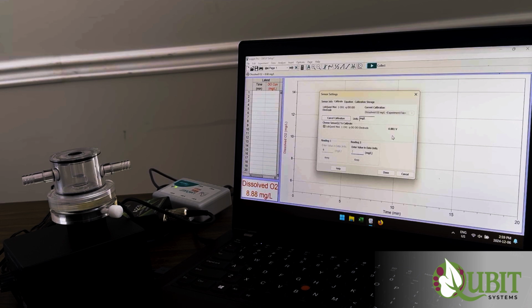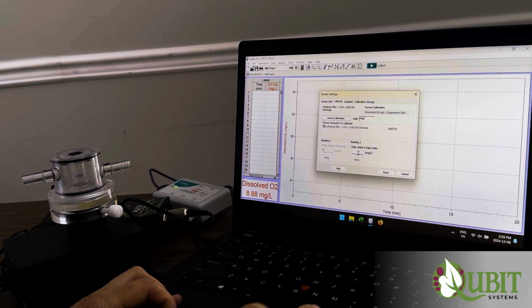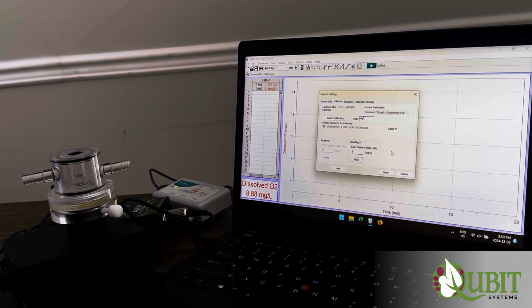So you wait until this voltage stabilizes, and under reading 2 you will enter 0 milligrams per liter, but don't click keep until the reading is stable. So you keep monitoring this voltage reading here. You know, it's at 8.59 now, so it's almost there, still dropping a little bit. And when that is stable, we will be assigning 0 milligrams per liter to this voltage. And that's the calibration that's going to be set up in the software, you know, for this particular setup of the oxygen electrode.